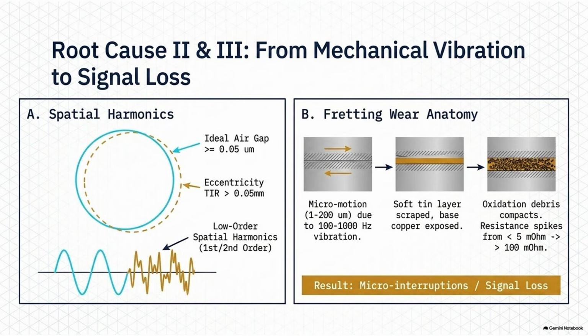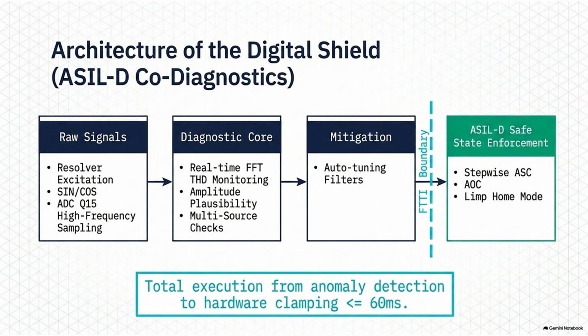So when those pins vibrate against each other by just a few microns, hundreds of times a second, that microscopic rubbing is what they call fretting. Exactly. And that fretting physically scrapes the soft tin layer right off the contact points, which exposes the base metal underneath, the copper. And copper has a massive weakness. When raw copper is exposed to oxygen and the trace amounts of moisture in the ambient air, it instantly oxidizes. It forms a layer of copper oxide. Right. But remember, the pins are still vibrating. So that new layer of copper oxide gets scraped off too. Yes. Then the freshly exposed copper oxidizes again and gets scraped off again.